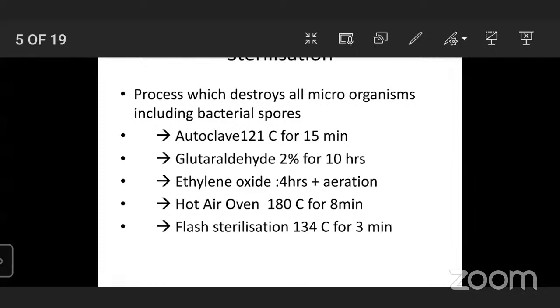Sterilization actually means the process which destroys all microorganisms, including bacterial spores. You can achieve it by autoclaving, by ethylene oxide gas sterilization of all tubings for a period of 4 hours along with aeration, and by a hot air oven. We commonly use a hot air oven in our NICU milk bank for sterilizing the steel containers used for dispensing milk to babies. You can also achieve sterilization with 2% glutaraldehyde if you allow a contact time for that equipment of more than 10 hours.